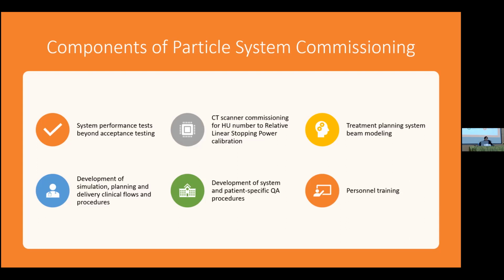Not going to spend too much time on it. I talked earlier about the dual energy CT scanners, but how is your CT scanning commissioning? We need to talk about that because these are also tools that you're going to use, whether you're going to do single energy or dual energy, what that means, and how that interfaces with your system. If you're doing a dual energy CT in a certain way, can the vendor's system actually accept it so you could do a cone beam and registration, etc.?